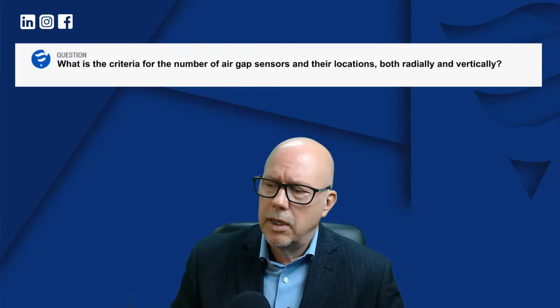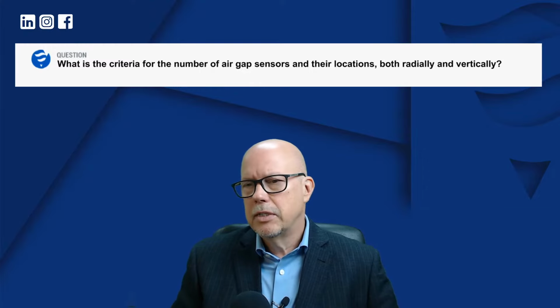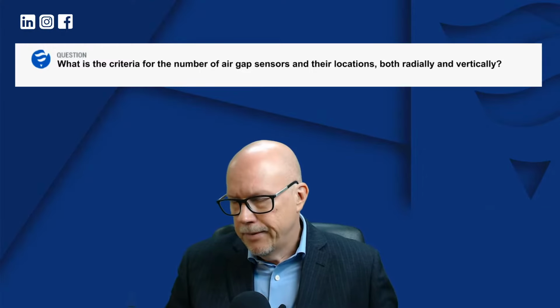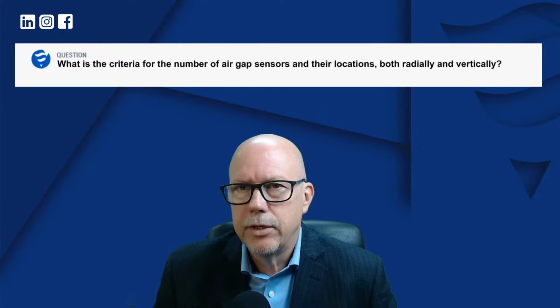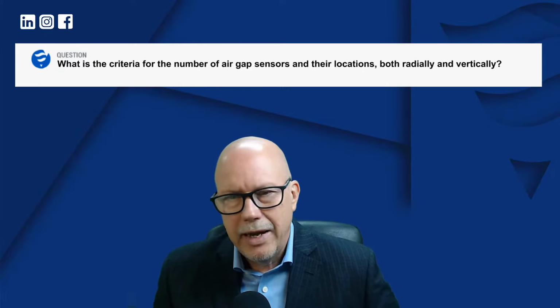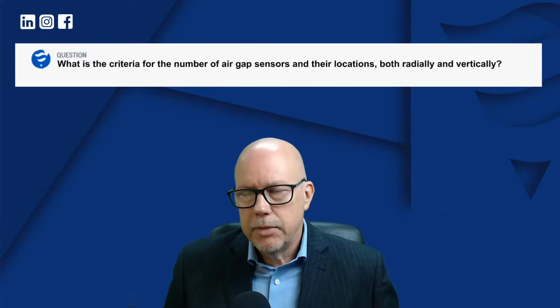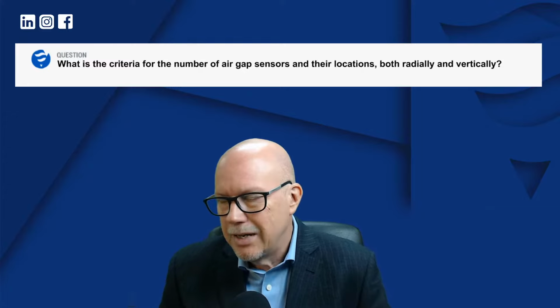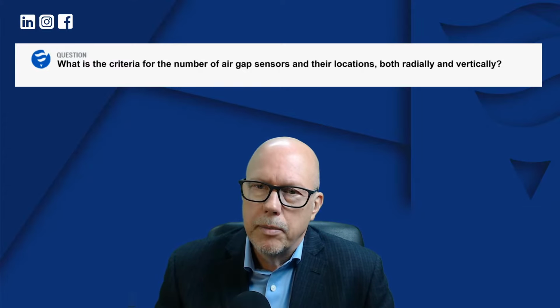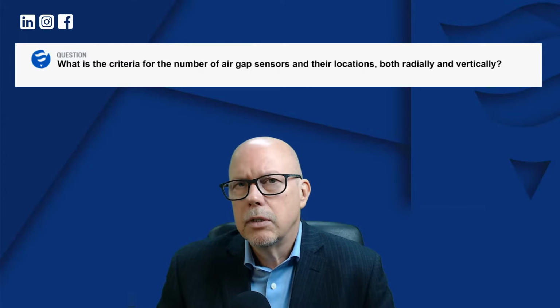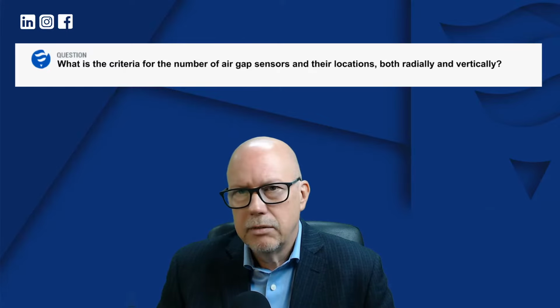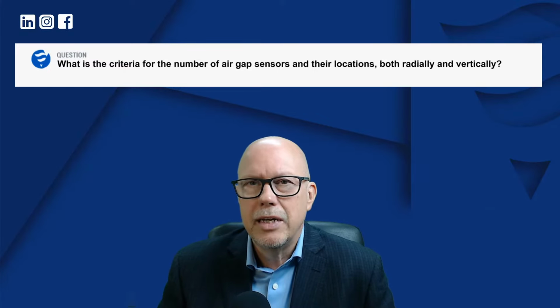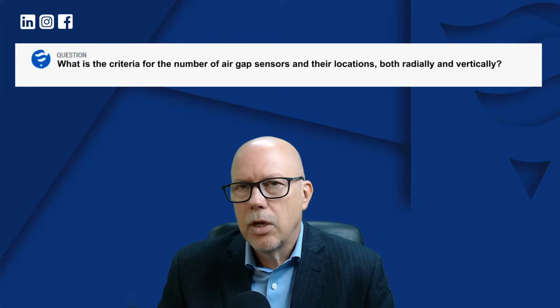If you have a stator that has a diameter of, let's say, more than 12 meters, you'll put 8. If it's more than 16 meters, you'll put 12. It depends on the size. And also, depending on the height, if your unit is, let's say, more than 1.6 or 1.8 meters, we would recommend top and bottom sensors.